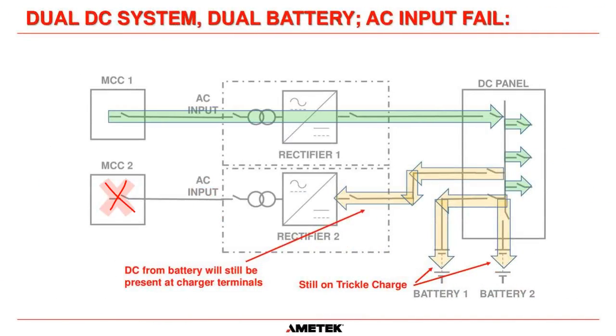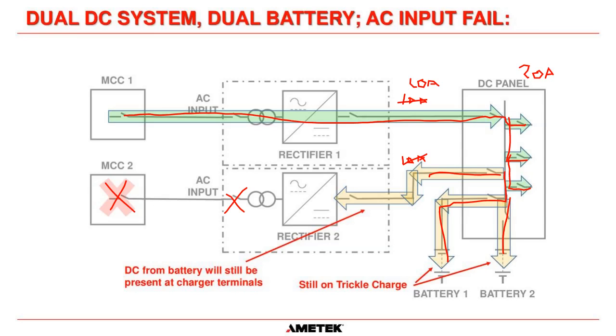So let's say we have a failure in MCC2. Therefore, we have no AC power going to rectifier 2. Well, what will happen is rectifier or charger 1 will continue without any switching whatsoever. It will just say, okay, I need to supply all the power now. So remember we said earlier, this would be 10 amps and this would be 10 amps. If we had 20 amps on the load panel, all that would happen now is instead of it being 10 amps there, it is now going to be 20 amps coming out of charger 1. And it continues to feed both batteries with its trickle charge. So both batteries are still being kept at their full charge voltage.